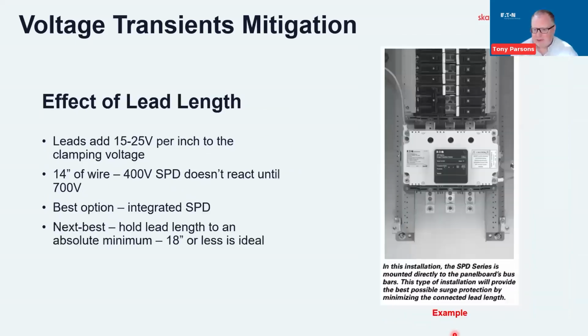To that end, the next slide shows probably the biggest problem that I see on low voltage surge protection, and that is the effective lead length. The picture on the right-hand side shows what would be called an integrated or integral surge protective device. We have a low voltage surge protective device mounted right on the panels or the bus bars inside a panelboard. That's the best thing. If you can directly connect to the terminals or the bus bars of the equipment you're trying to protect, you get the best degree of protection. What if we can't mount it there? You can't always do that. Then you have a lead or a conductor going out, connecting from the panel or MCC or whatever to the surge protective device. You want to keep that lead length as short as possible. Again, we talked about the impedance making a difference.